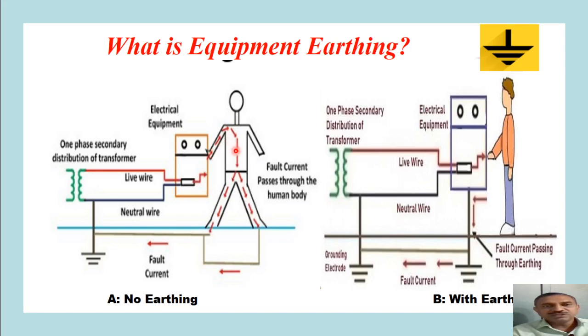The person who is touching this electrical equipment under faulty condition will now be in direct touch with that live wire or phase voltage. As the person is standing on the ground, we can observe here how the current will flow from the electrical equipment body. It will flow through the hands, then the body of the person, then through both legs. The current will return back to the ground and finally flow through the neutral wire. So the circuit is completed. When such a current flows through a person who is touching that faulty equipment, an electric shock will be experienced by him, and this must be avoided in order to save the life of that person. How can this be saved?